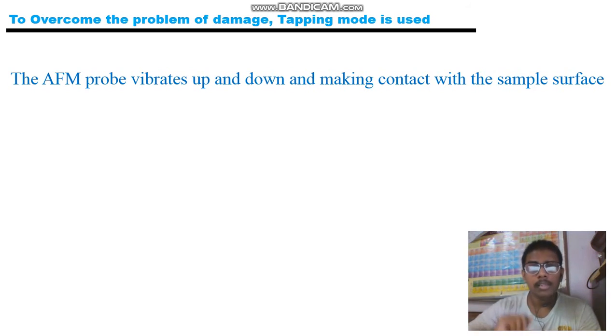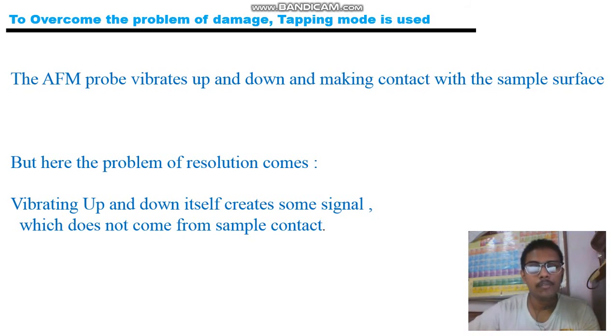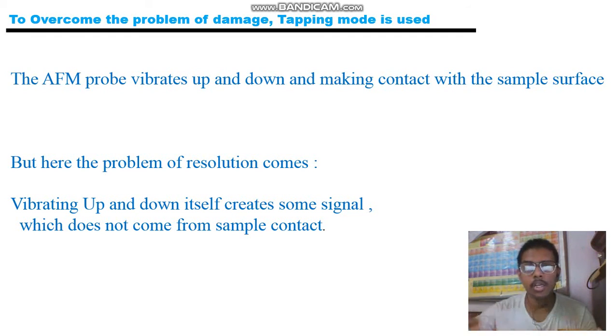To overcome the problem of surface damage, people have proposed tapping mode, where the AFM probe is actually vibrating up and down and not in contact with the surface for a longer time. Thus you can avoid contact with the sample surface for longer periods and avoid damage to your sample. However, one problem is that when the probe goes up and down, it can by itself generate some signal that doesn't come from sample contact with the probe, so there is a chance of false signal generation. In perspective of resolution as well as faithfulness of the sample signal, people prefer the contact mode compared to non-contact mode.